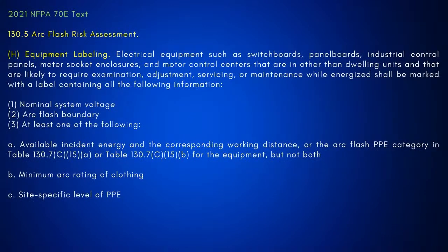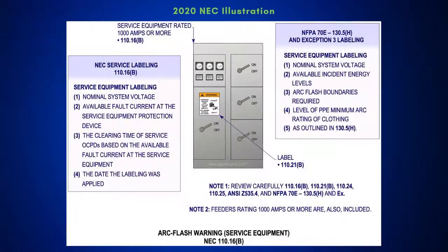Okay. So the next thing we looked at was 130.5H, and this is in the 2021 70E document, and this deals with equipment labeling. If you read that, it reads almost exactly like 110.16B, except they talk about the label containing the following information: your nominal system voltage, your arc flash boundary, and at least one of the following. You have your available incident energy and the corresponding working distance, or you can have the arc flash PPE category that's in those tables, 130.7(C)(15)(a) or (b), for the equipment, but you can't have both. It'll be one of the two. And then you'll have your minimum arc rating of clothing and your site-specific level of PPE. Now, whichever is greater: if there's a standard that's greater, then you need to follow it.